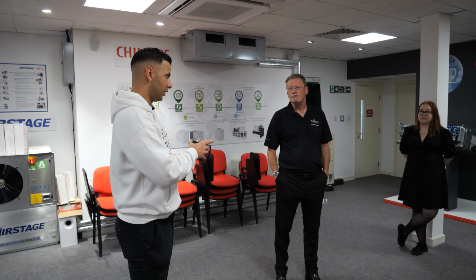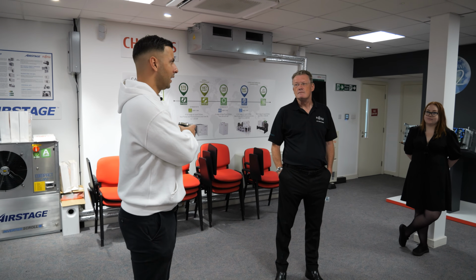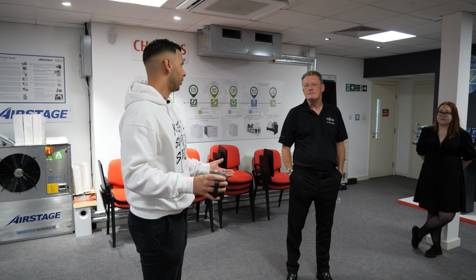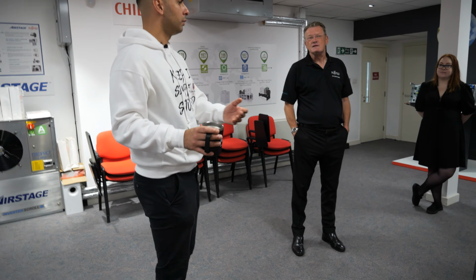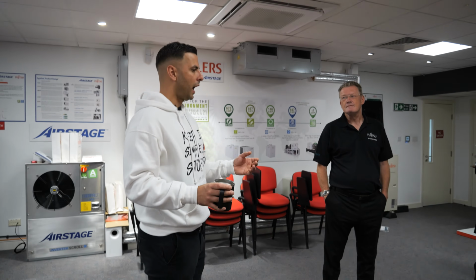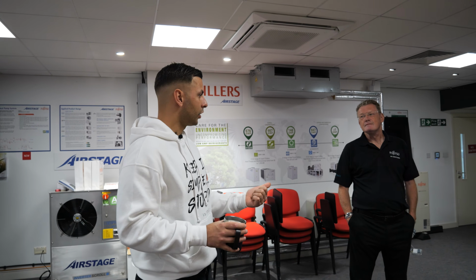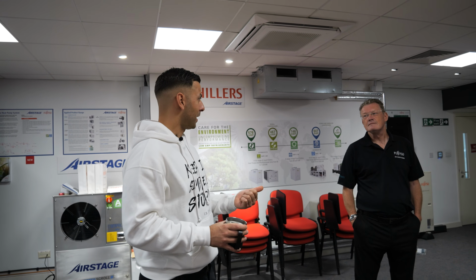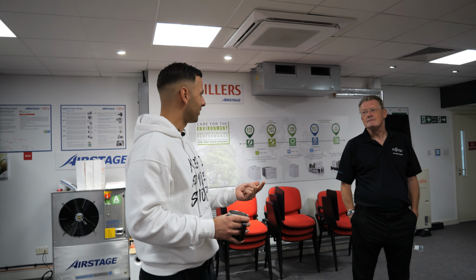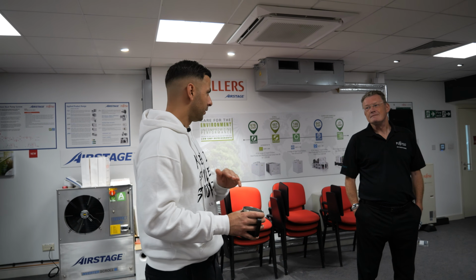Is yours similar, or are you more like the bigger ones, where the cost is the cost? Because we've had clients have one of the two manufacturers, the top two heat pumps, put in. They've had a leak on the heat exchanger, which was repaired by the manufacturer. The compressor failed six months later. Obviously, we had a water to refrigeration breach. And if you're a fridge engineer, you know it's just done.